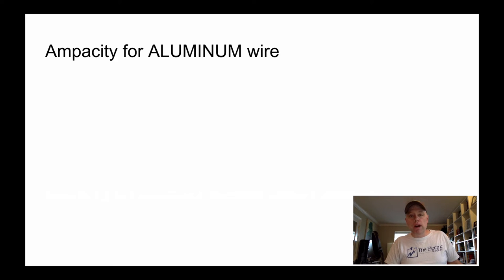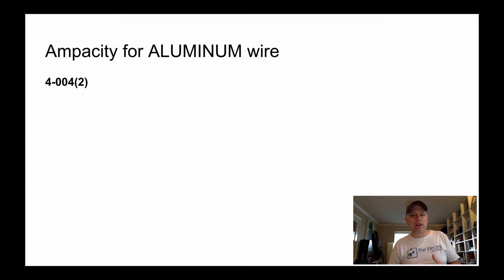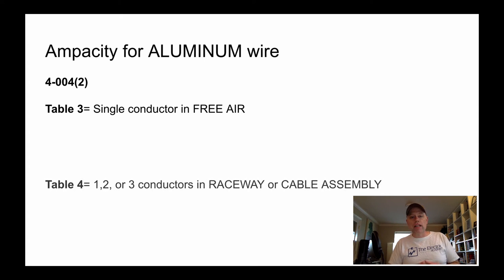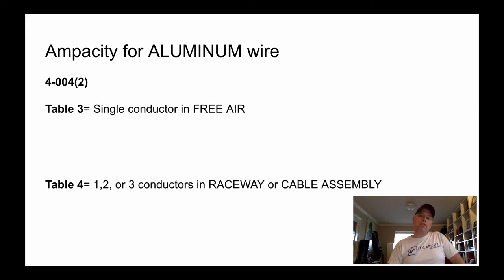The ampacity for aluminum wire follows the same ideas and is found in 4-004 subrule 2. Aluminum handles a slightly different ampacity than copper, so the tables are different. For a single aluminum conductor in free air, we use table 3. For one, two, or three aluminum conductors in a raceway or cable assembly, we use table 4. The important part is recognizing whether you're dealing with aluminum or copper wire, because your tables are totally different.